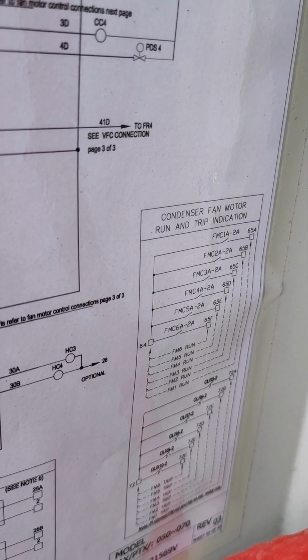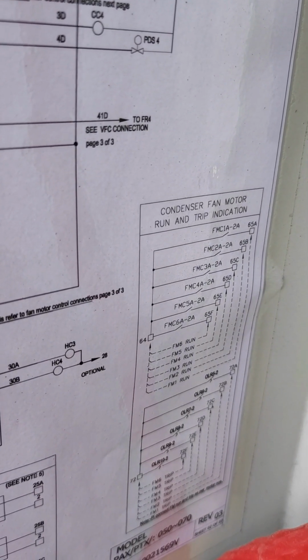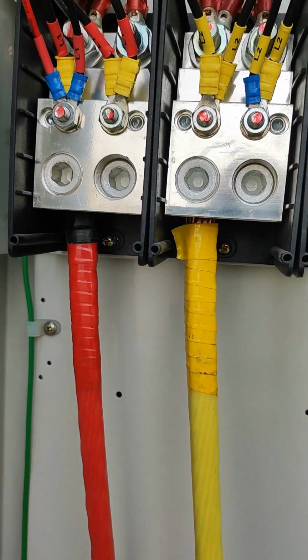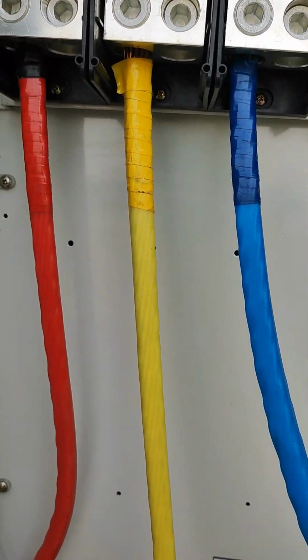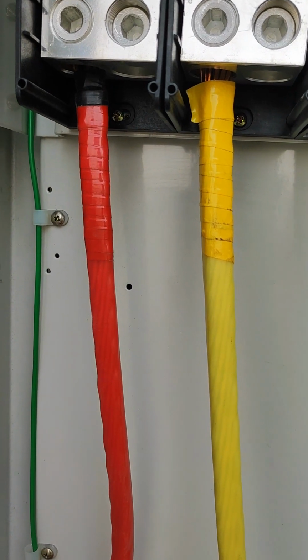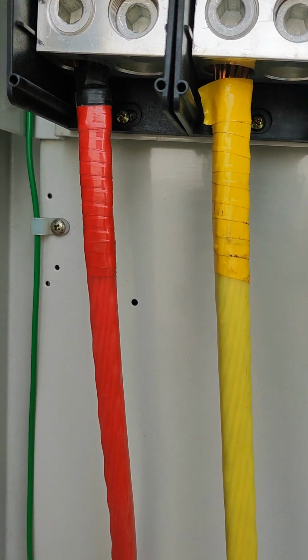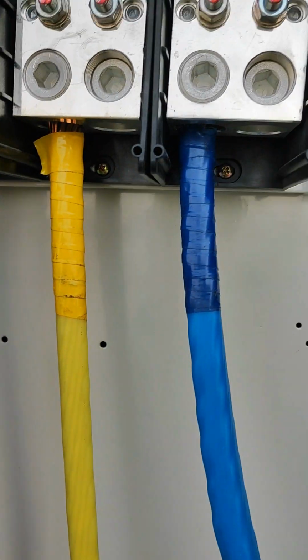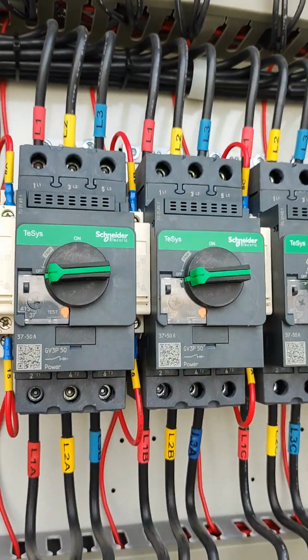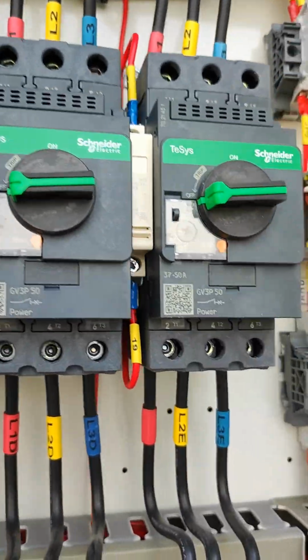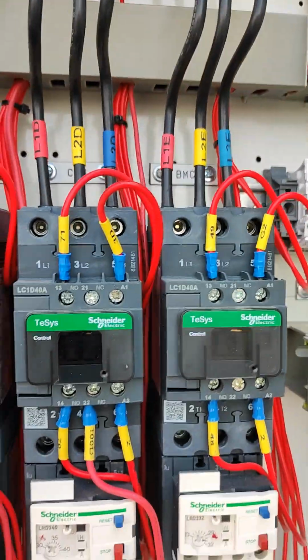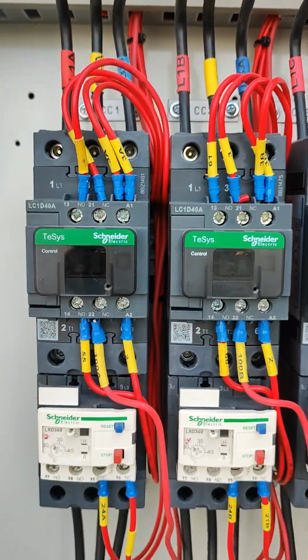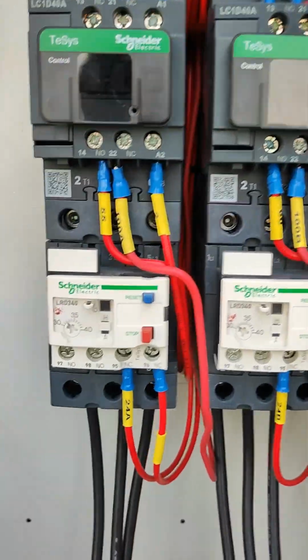The solenoid valve first energizes, then the blower motor, then compressor number 1 solenoid valve, then demand to the compressor like this. Condenser fan motor also. This is the main power supply coming from the MCC, from the disconnect switch to the unit.